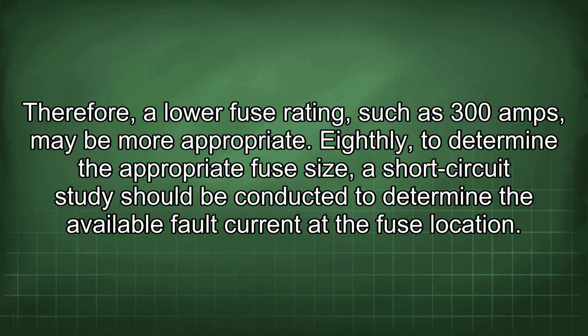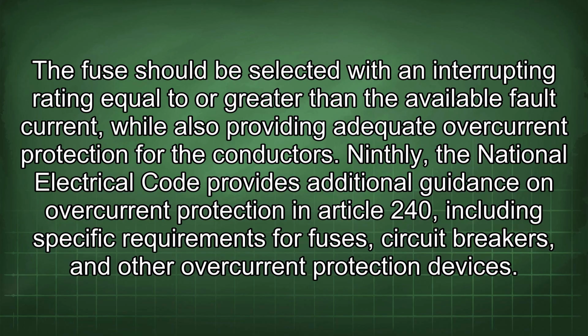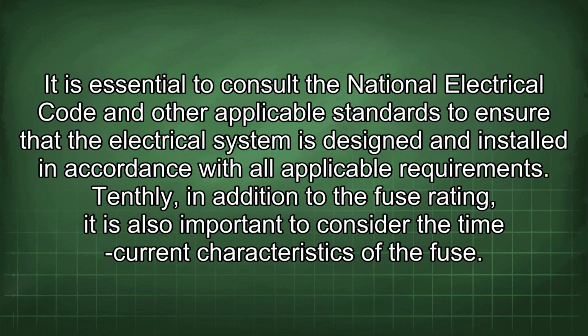Eighthly, to determine the appropriate fuse size, a short-circuit study should be conducted to determine the available fault current at the fuse location. The fuse should be selected with an interrupting rating equal to or greater than the available fault current, while also providing adequate overcurrent protection for the conductors. Ninthly, the National Electrical Code provides additional guidance on overcurrent protection in Article 240, including specific requirements for fuses, circuit breakers, and other overcurrent protection devices. It is essential to consult the National Electrical Code and other applicable standards to ensure that the electrical system is designed and installed in accordance with all applicable requirements.